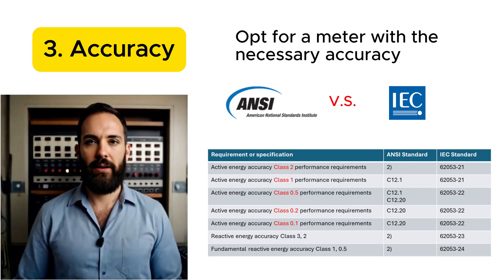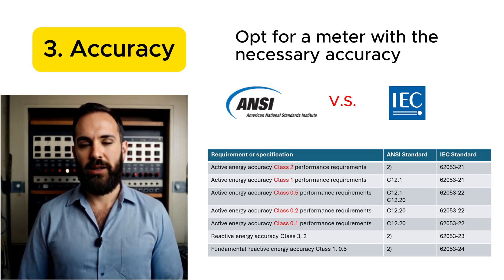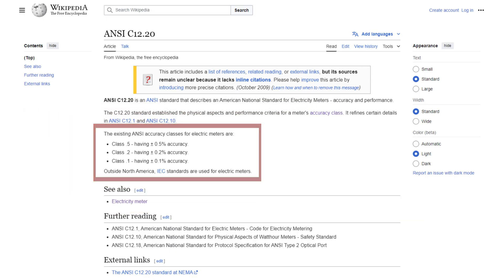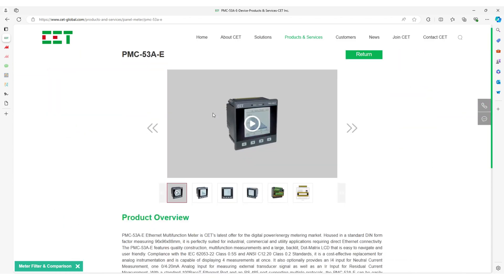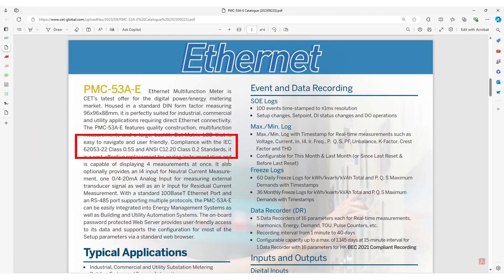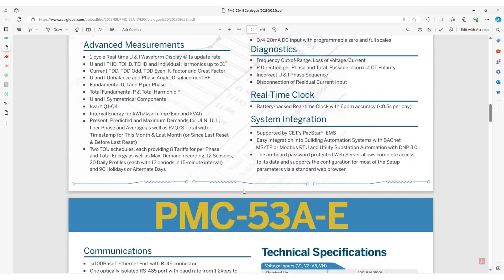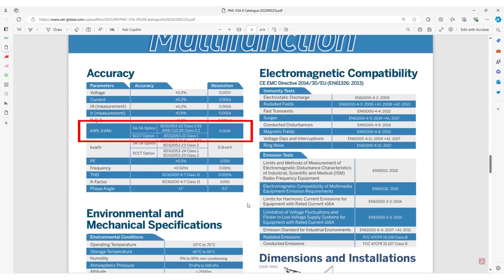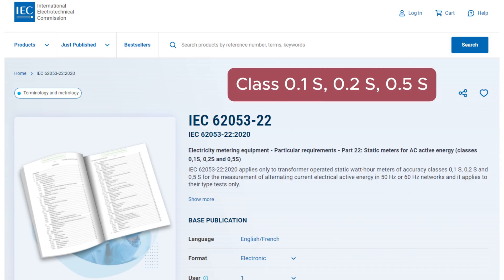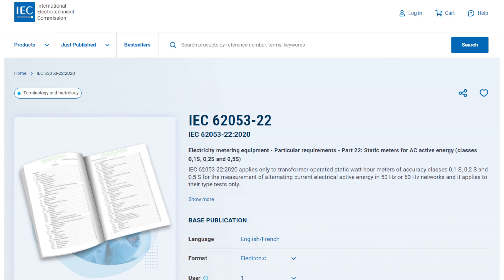Number three: accuracy. Opt for a meter with the necessary accuracy. ANSI C12.20 defines the accuracy requirements for revenue-grade meters with accuracy classes of 0.1, 0.2, and 0.5. These classes indicate the percentage error allowed in the meter's readings. Similarly, IEC 62053-22 specifies the requirements for static meters for active energy, for example class 0.5s and above, ensuring high accuracy in energy measurement.